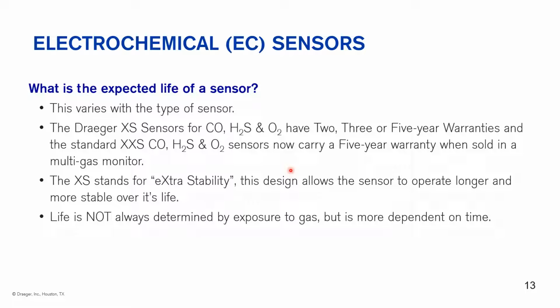So the expected lifespan of a sensor will vary. We do have sensors with very long warranties: CO, H2S, and O2. But just because they have a long warranty doesn't mean that that's all that they will last. We fully expect these sensors to last well beyond a 5-year period. Life isn't always determined by the gas exposure, more dependent on time and environmental issues. There are exceptions. An ammonia sensor, for example, does have a dependency on the lifespan being determined by how much gas that sensor does see over its lifespan.